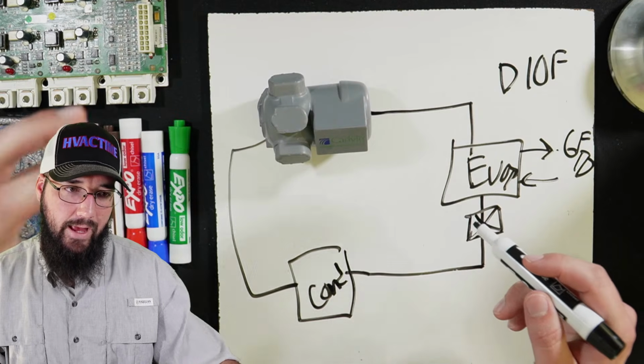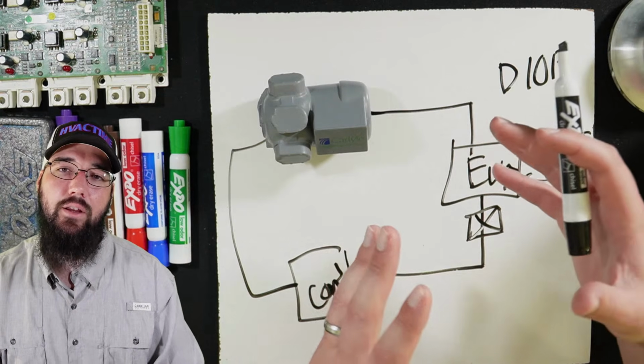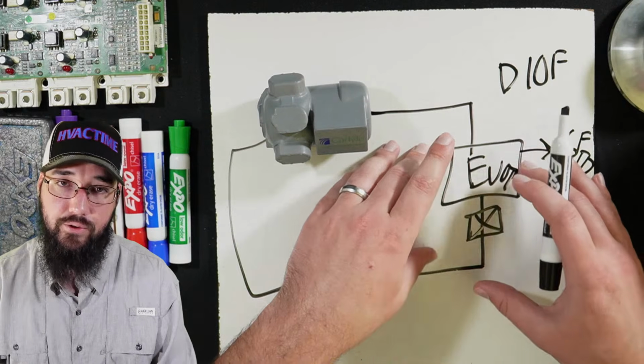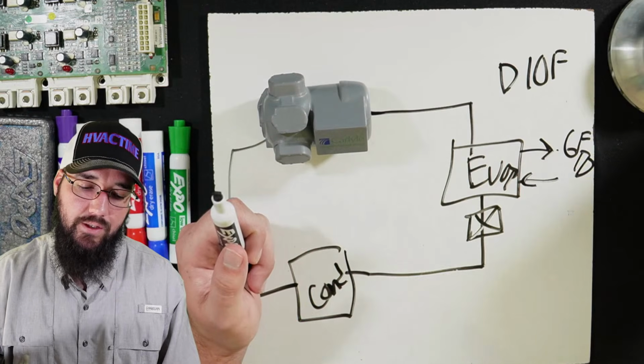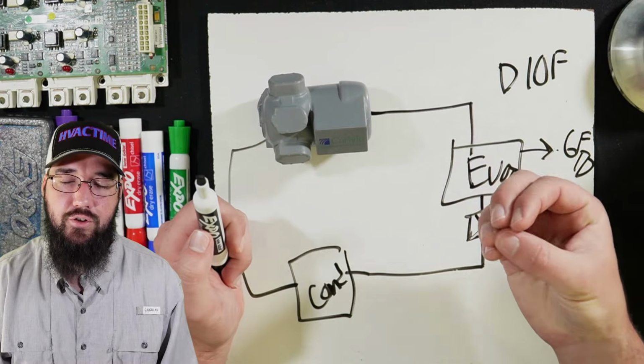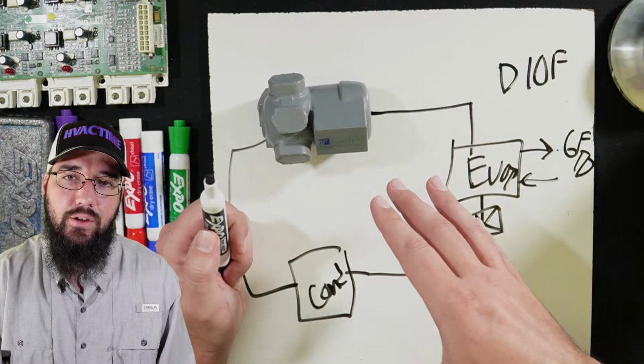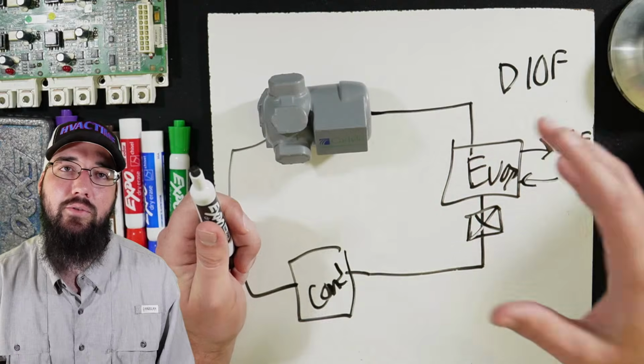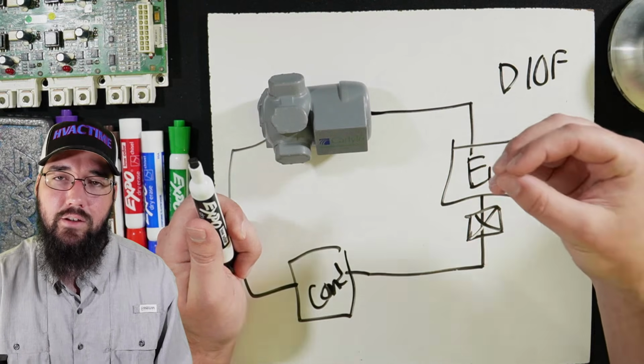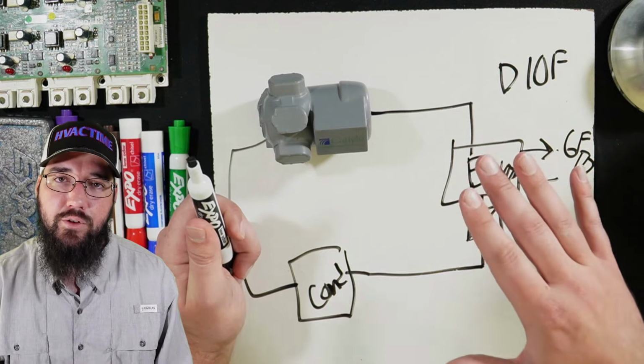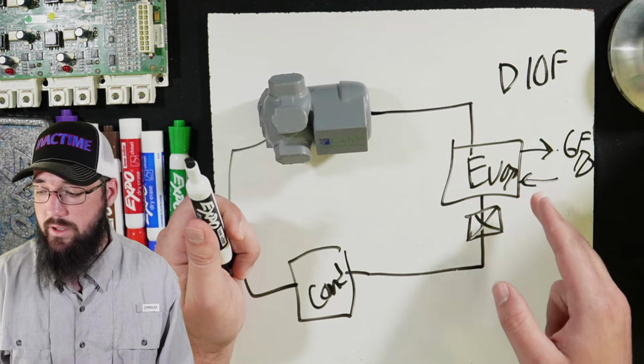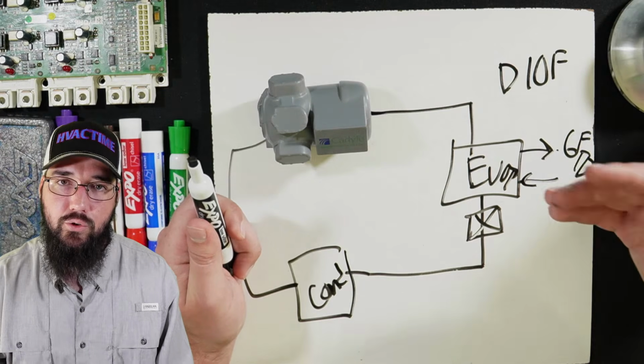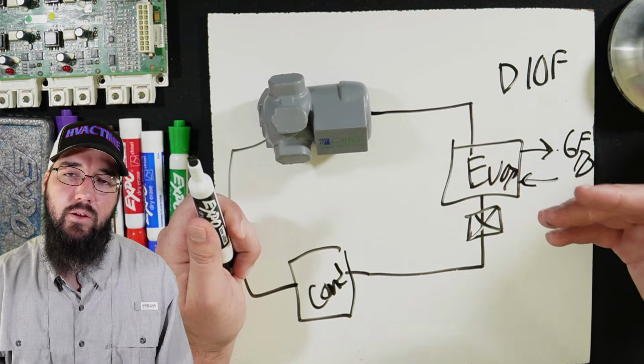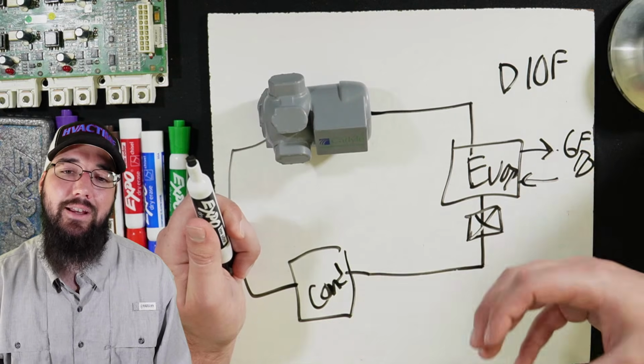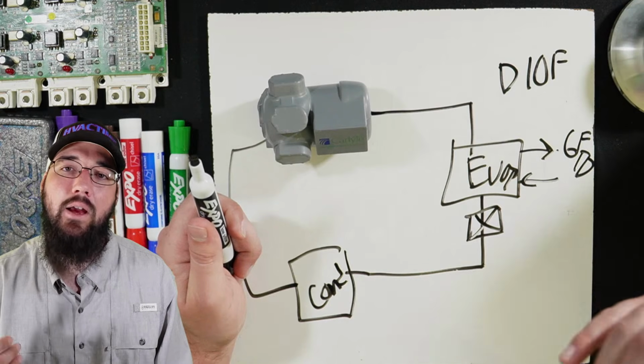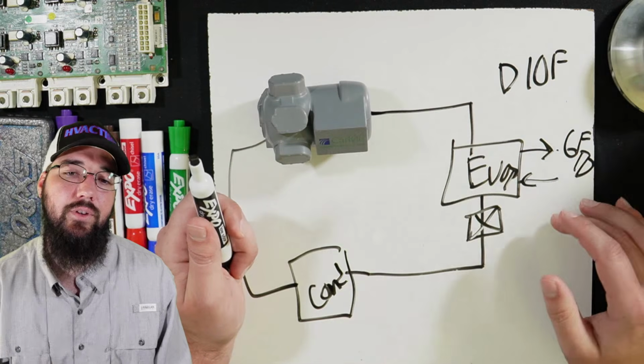So as we need to remove less heat, we need to add less heat to the refrigerant. This process allows us to slow down that rate of exchange. We don't need to give the heat as fast, or as much volume of heat, from the water to the refrigerant, because we can reduce the total BTUs needed. We can reduce how much temperature difference we have between saturation and the water. And because we can reduce that temperature difference, that is reducing approach. So the approach is just representing how much difference is needed to achieve the BTUs we're asking of it. That's why at full load, we have a 10 degree design approach for this evaporator.